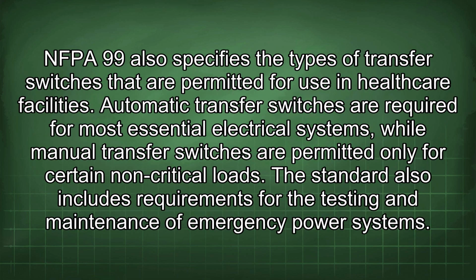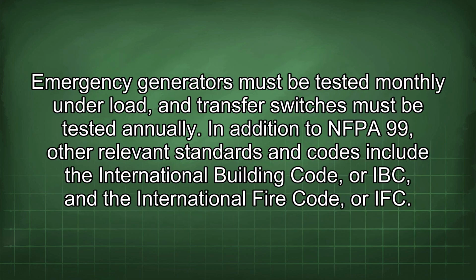NFPA 99 also specifies the types of transfer switches that are permitted for use in healthcare facilities. Automatic transfer switches are required for most essential electrical systems, while manual transfer switches are permitted only for certain non-critical loads. The standard also includes requirements for the testing and maintenance of emergency power systems. Emergency generators must be tested monthly under load, and transfer switches must be tested annually.